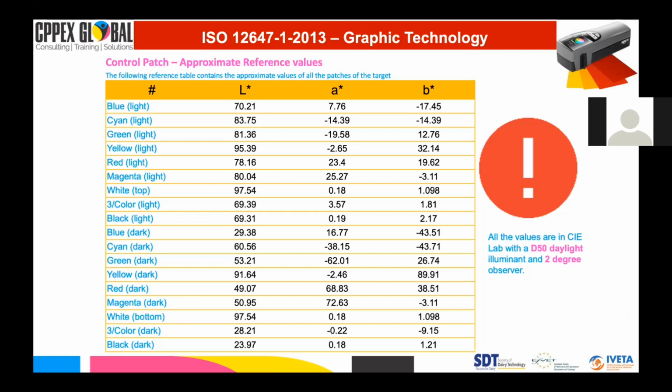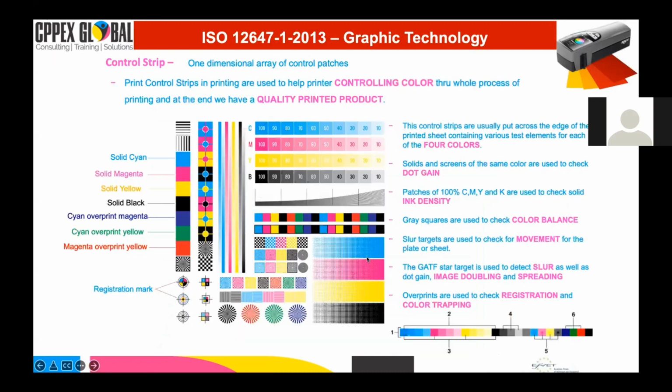And I've worked and visited customers, and we don't really know what these settings are. And so we don't pay attention that they're set, and they do change the value. And this could be the difference between a pass and a fail. So please know what these are and make sure they're set to the numbers that you want them to be set at. And D50, 2 degrees, is normally what we would like them to be at, unless there's a reason to have them at another value.